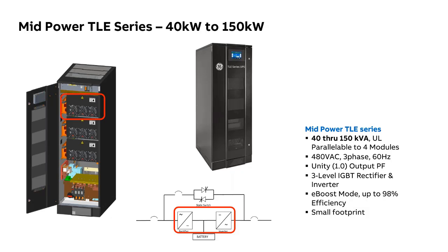The module is just a rectifier and inverter. It's just the power module. There's nothing else. Everything else is centralized in the frame: the static switch, the control logic, the display, everything else. And it is a power module, but it's bolted in. So the reason for this design, and this is not unique to ABB.